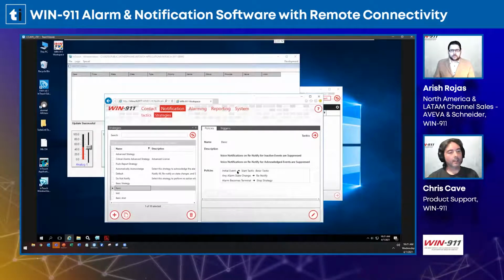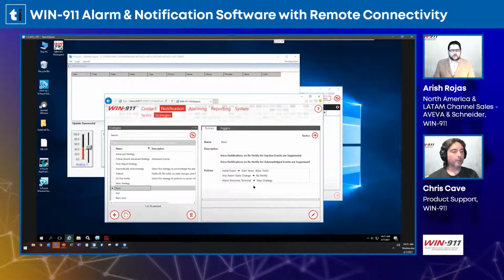The initial event is the alarm triggering. It will start a tactic, which is a call-out list. If any alarm state change occurs, it will re-notify, and we'll stop the call-out list once the alarm becomes acknowledged and returns to normal. We also have another option to stop the call-out list once acknowledged.